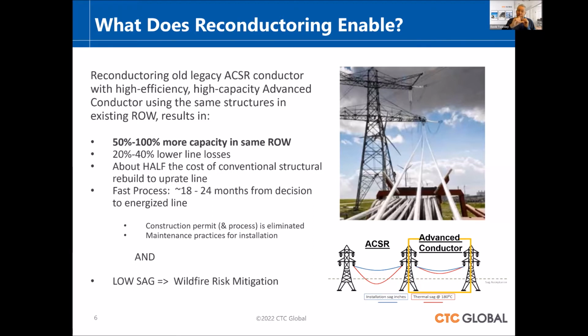And that line, because it's using these advanced conductors, has much, much lower sag. The picture on the right suggests very little sag, which enables a number of different applications, but certainly enables wildfire risk mitigation. We've seen that with anecdotal information, particularly out west.